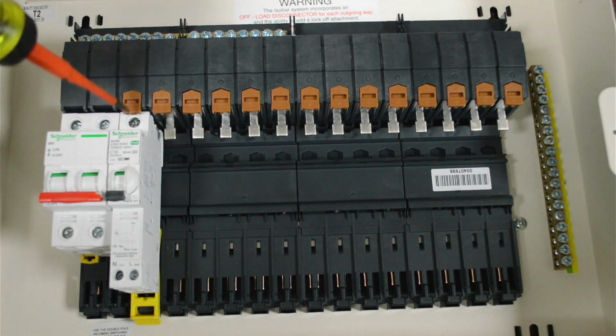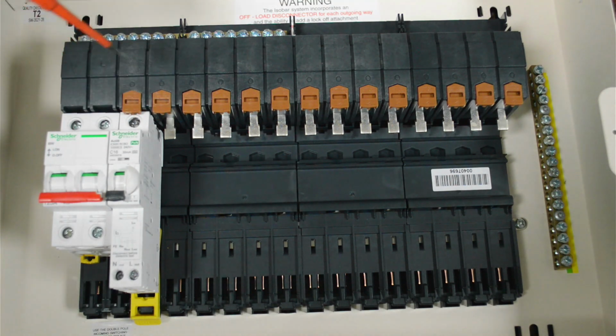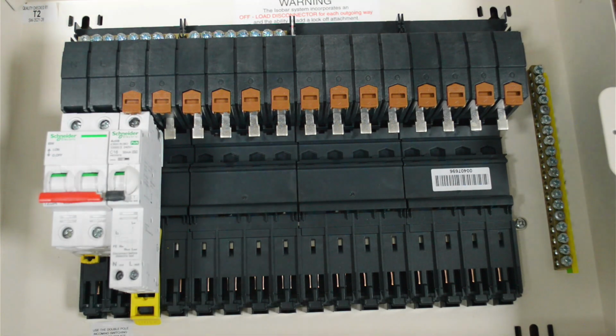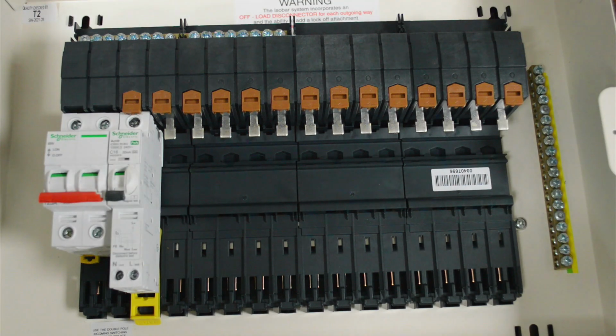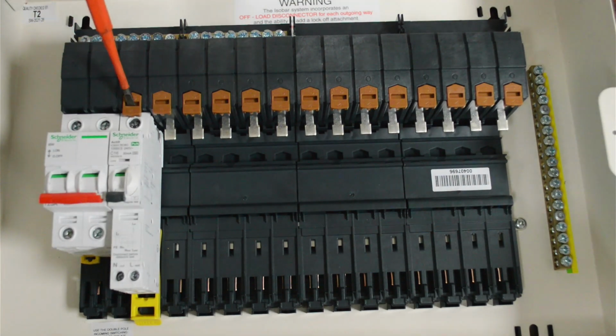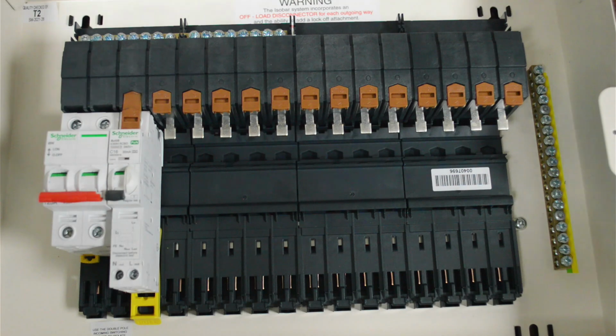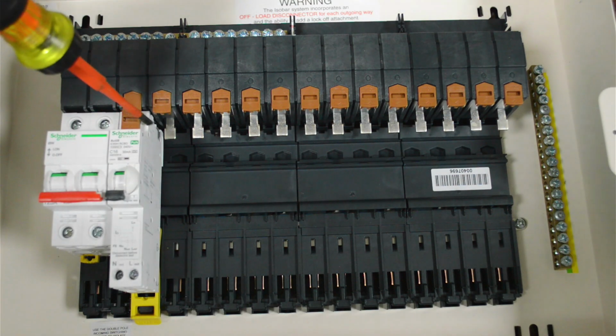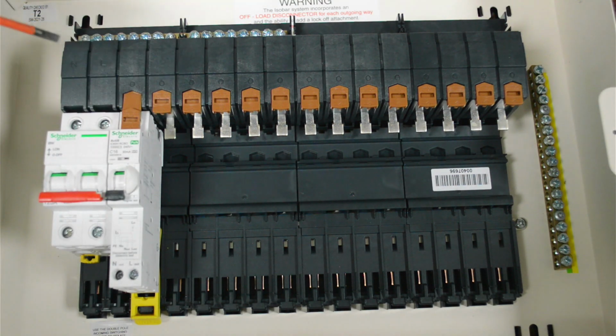and that's it now clamped. Now obviously you would tighten down this terminal here, so you've got an effective connection onto the line busbar, and then obviously your final circuits would be wired into the neutral and the line on the outgoing side of the RCBO. Now if you don't move this tab out, you see that covers the actual screw terminal on the bottom of the RCBO.